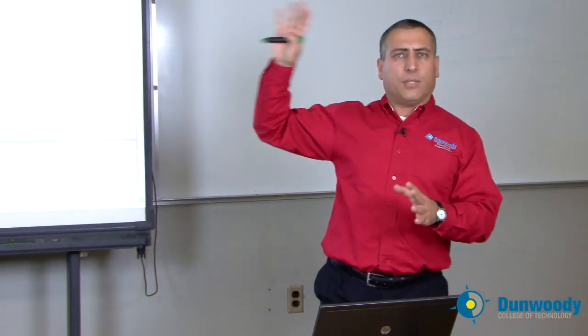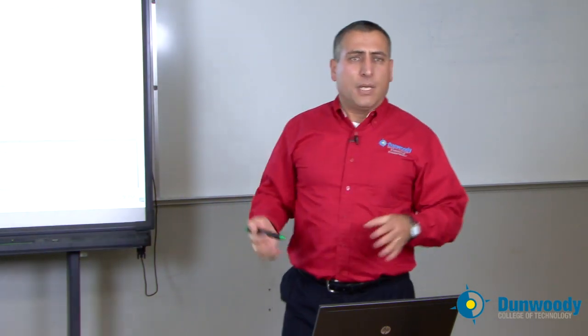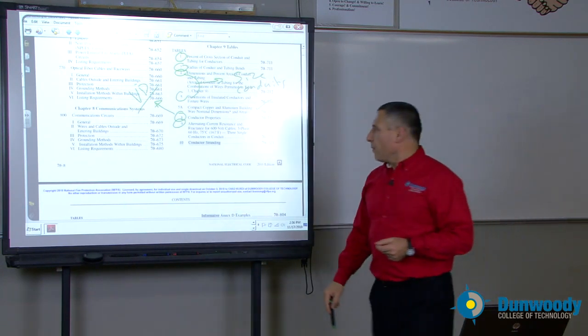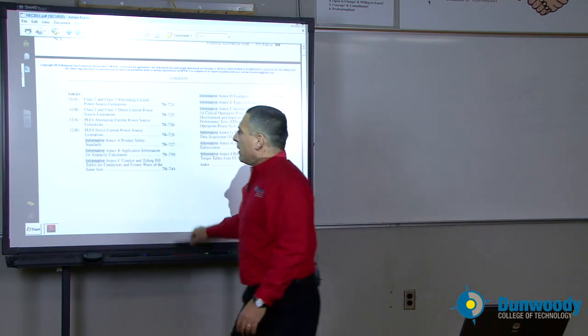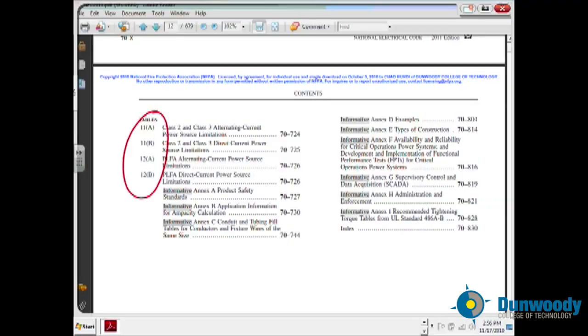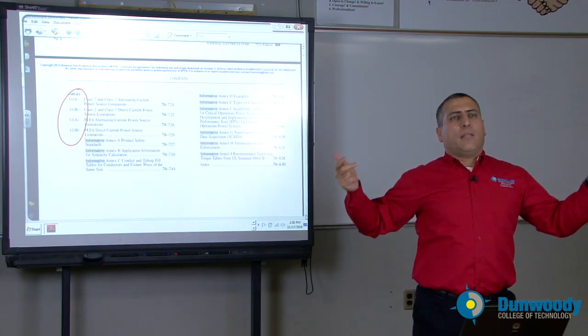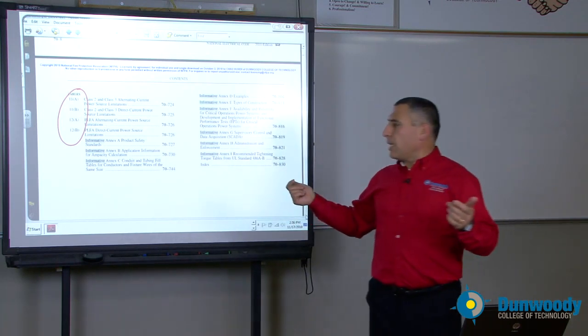How far can I push a 100-amp panel away from the source and still meet the code recommendation of 3% voltage drop? So these are basically the tables at the end of the code — very important tables. And for control systems, there are also tables covering Class 1 limitations of power and voltage, and Class 2 and Class 3 circuit limitations. How much current, voltage, and power can you get from a Class 2, Class 3, or power-limited fire alarm system? You're going to find it in these tables.